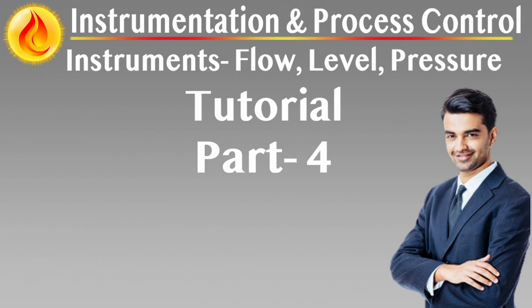Installation guidelines. Insert the probe into the center of the pipe or duct, 60 millimeters or more into the flow, avoiding contact with the opposite wall. Maintain correct alignment to the flow axis, typically perpendicular to the flow direction. Avoid high vibration points or locations near pulsating gas sources. Probes must be removed prior to flushing, steam out, or air blowing to prevent sensor burnout. Retractable assemblies are recommended for on-stream removal and cleaning, especially in dusty environments or continuous operation.